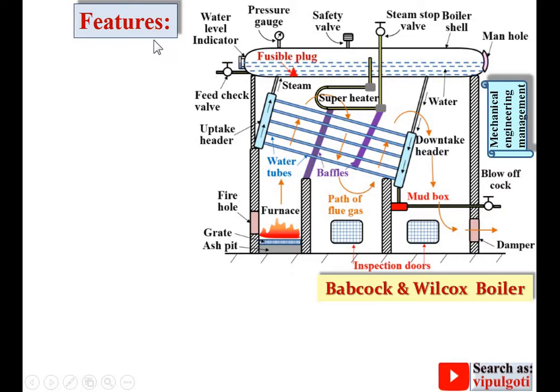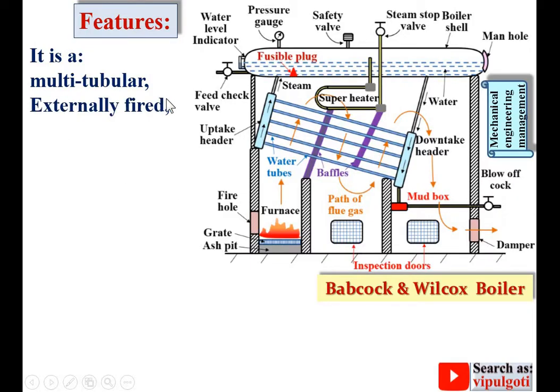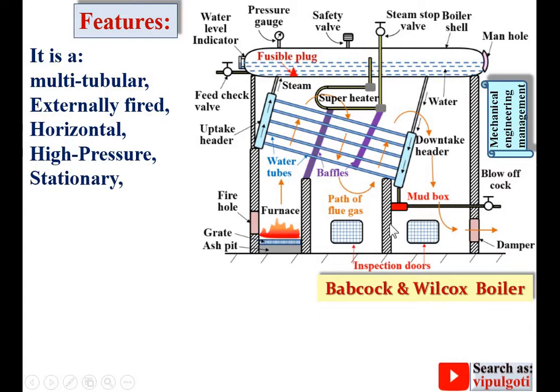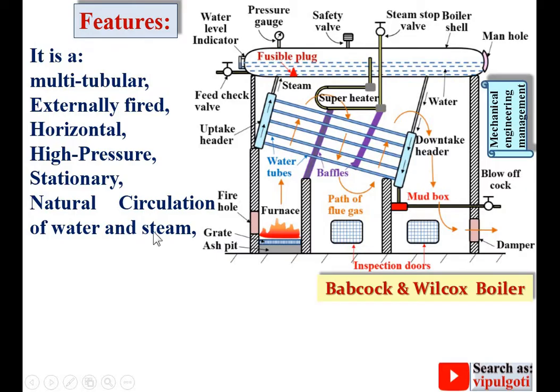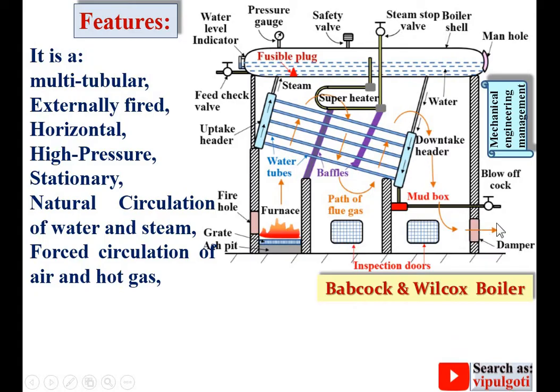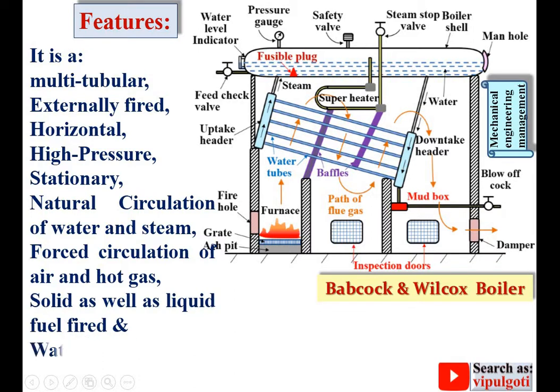First, the features. It is a multi-tubular boiler, as you can see there are a number of tubes. It is an externally fired boiler because the fire is outside of the boiler shell. The boiler shell is in a horizontal position, so it is called a horizontal boiler. It is a high-pressure boiler and a stationary boiler — it cannot move from one place to another. There is natural circulation of water and steam due to density difference, and forced circulation of air and hot gases via a chimney that creates pressure to move the flue gases. It is solid as well as liquid fuel fired, and it is a water tube boiler because water is inside the tubes and flue gases are outside.